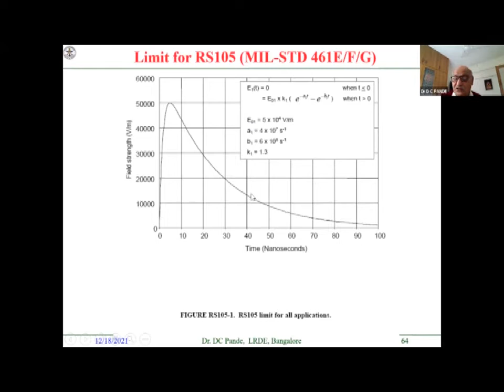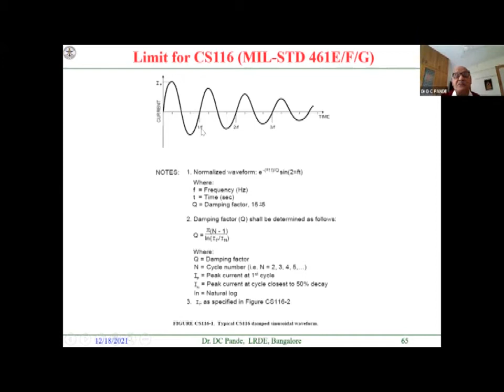One of the tests involves generating a 50,000 volt per meter field for the type of system to be protected. Then we have conducted damped transients that we inject inside the system, using this type of waveform.